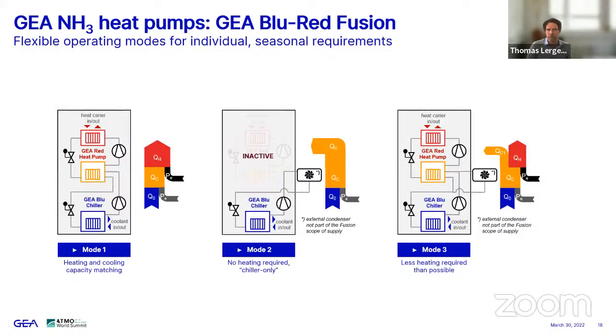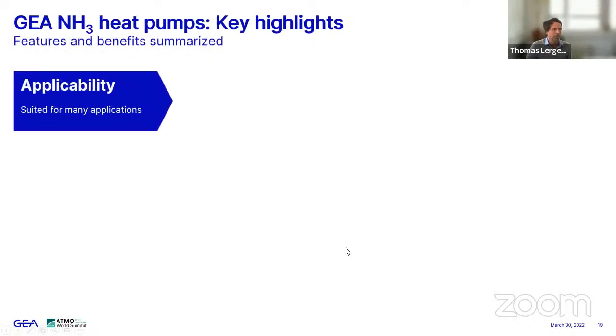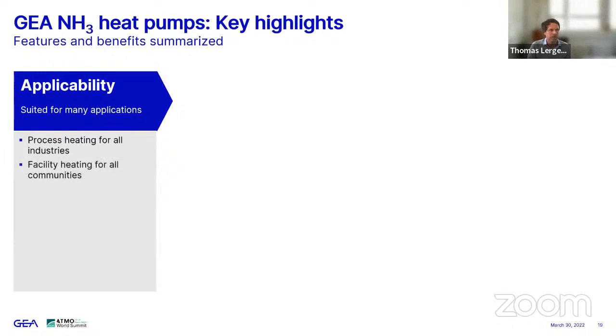Time to wrap up with a few key highlights of our heat pumps, some of the features and benefits summarized. First of all, the applicability. It's suited for many applications: process heating for all kinds of industries, and facility heating demands for all kinds of communities. The heat source can be handled with all common liquids. It doesn't have to be non-corrosive water. It can be glycols or even corrosive water, you name it. The minimum outlet of this liquid heat source would be -10 degrees Celsius.